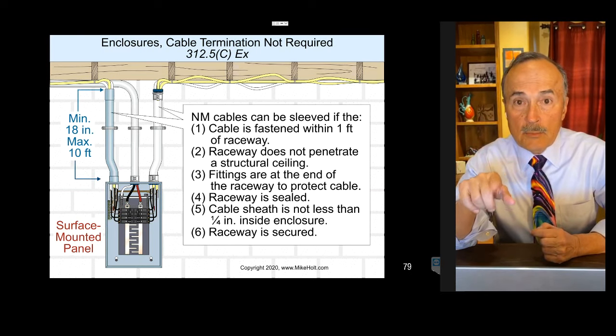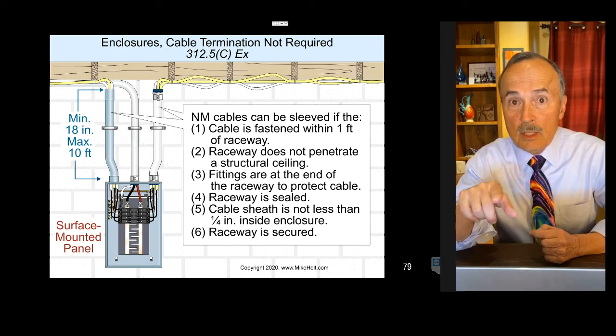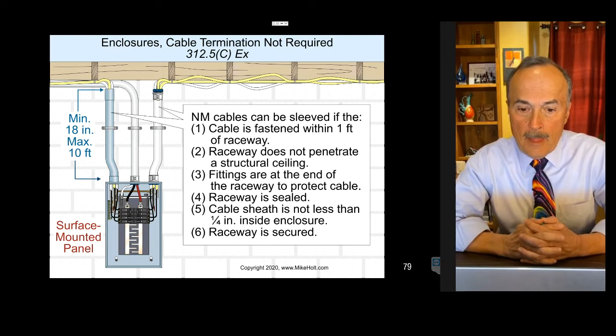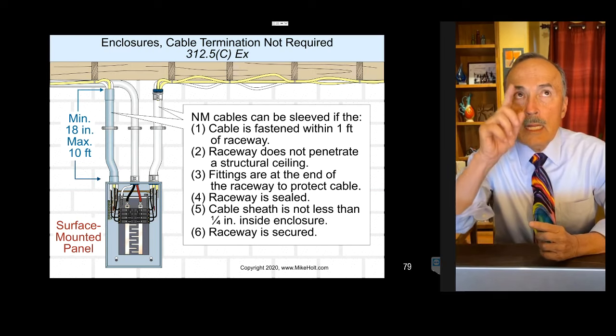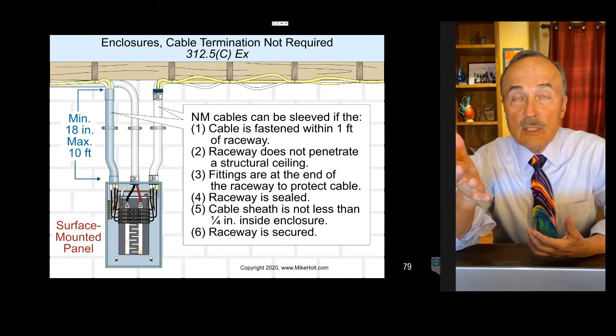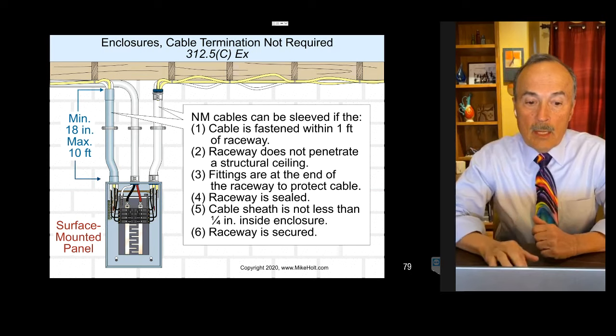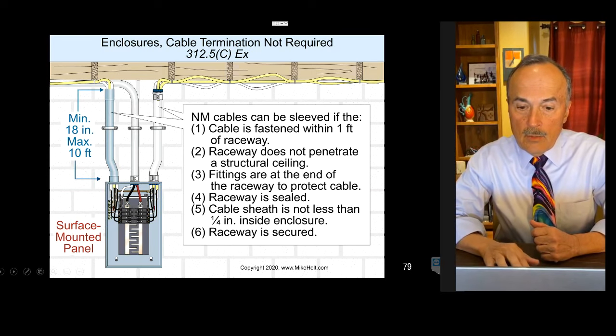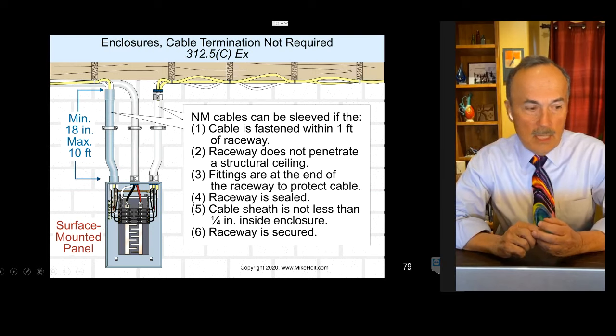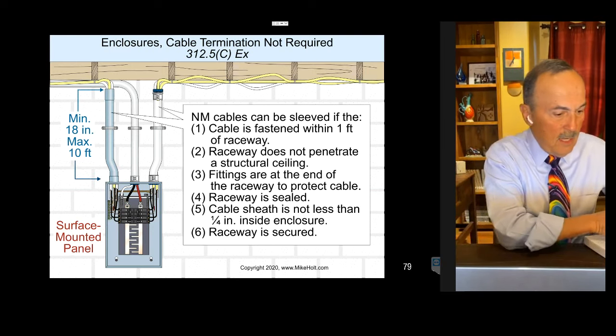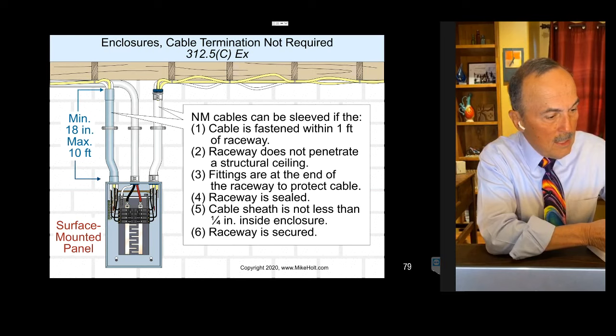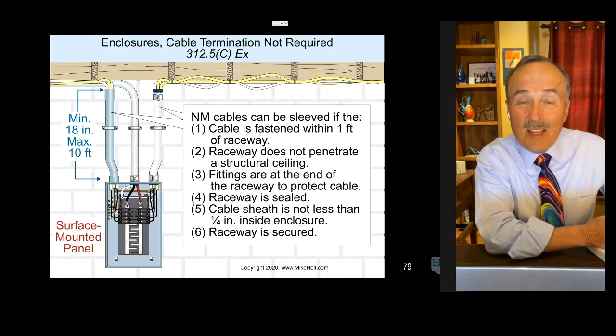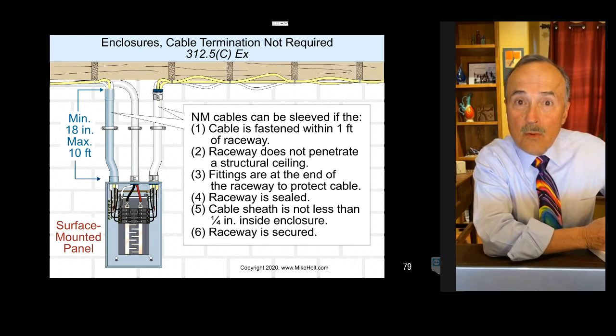To me, if I was the inspector, you got a piece of PVC, whatever you put on the end, I don't really care, or nothing. And then it goes on, the raceway is sealed. Okay, so you take a little foam, make sure you use foam that's not going to damage the conductor, and it's specifically identified to be used with electrical conductors. That's another rule. The cable sheath is not less than a 1/4 inch inside the enclosure, not less than a 1/4 inch. I could put 10 inches in there if I want to. Okay, probably not, but you have to have that in there. And the raceway is secured.